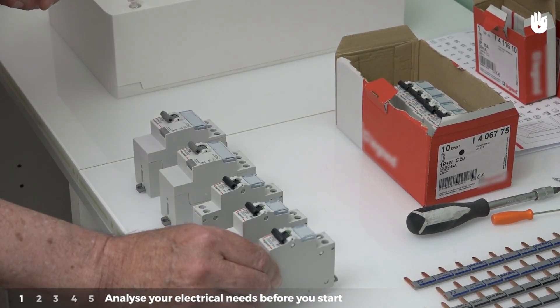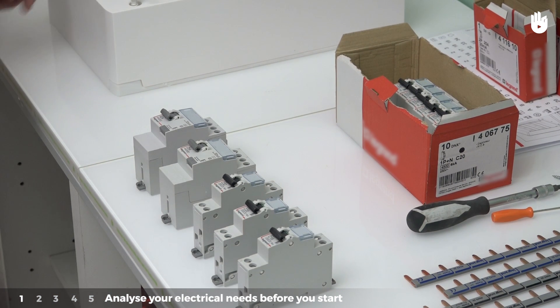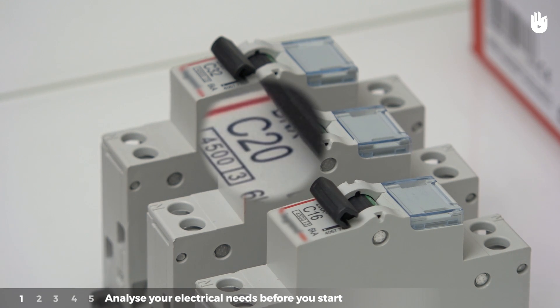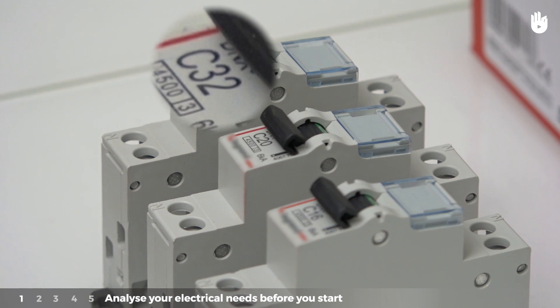These individual circuit breakers are calibrated according to the circuits they will protect: 16A for lighting, 20A for outlets or domestic appliances like washing machines, 32A for a hot plate or electric stove.